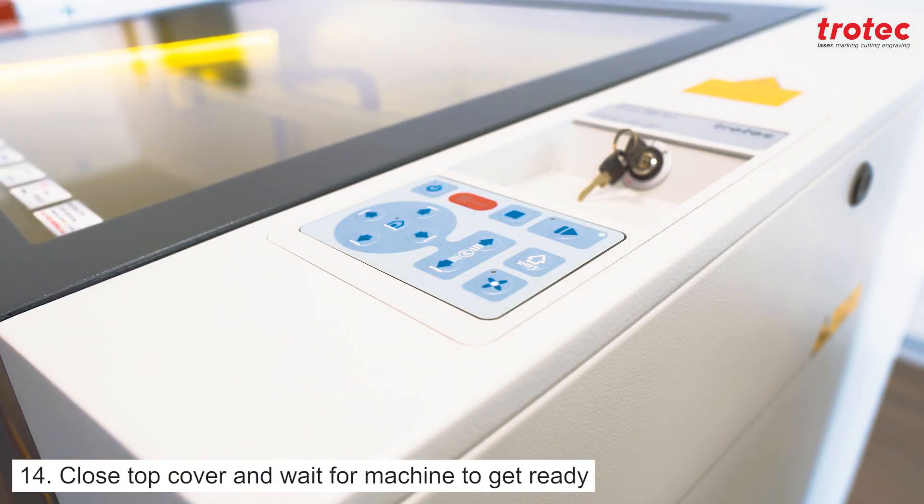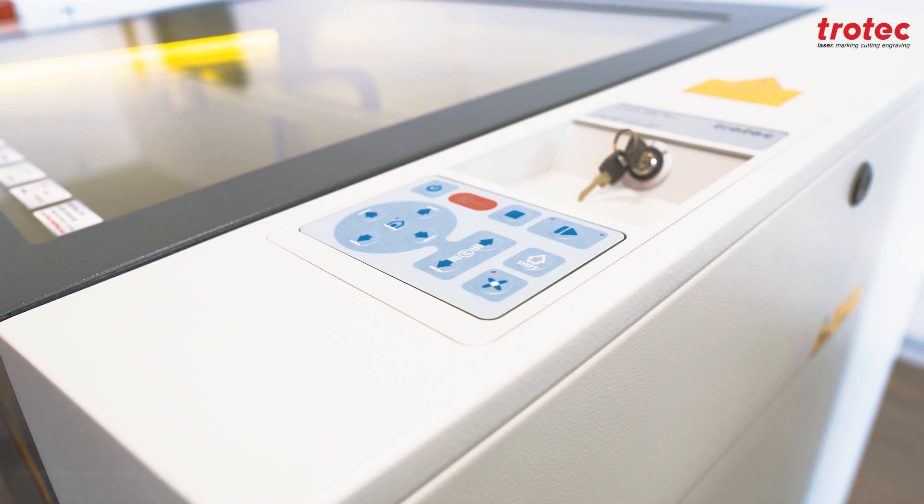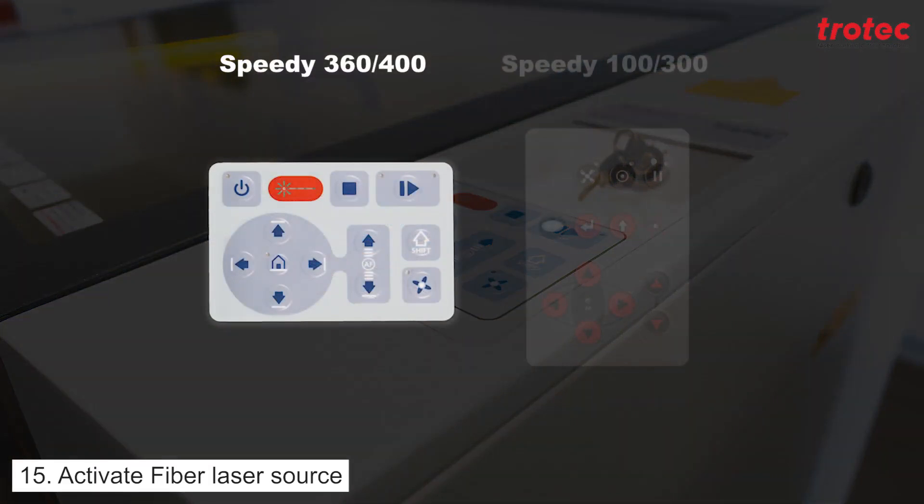Close the machine cover and wait for the machine to get ready. For the speedy 360 or 400 to activate the fiber laser source press the standby button here. Then press the y-axis arrows simultaneously.